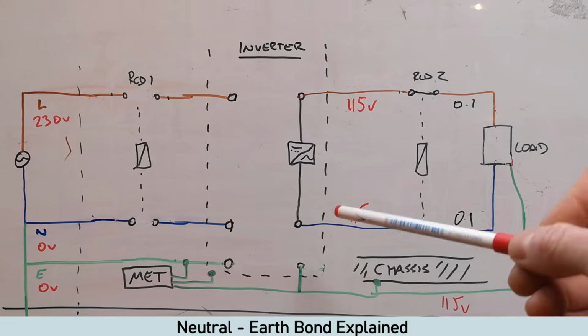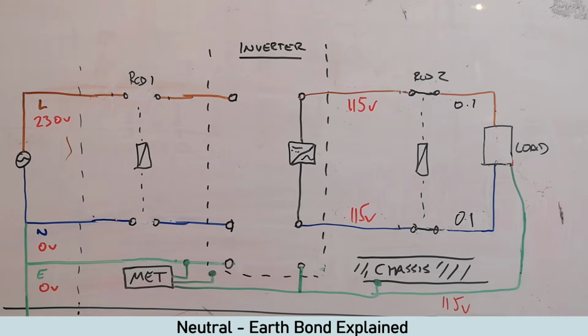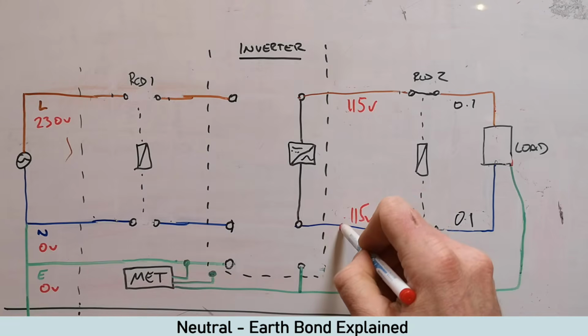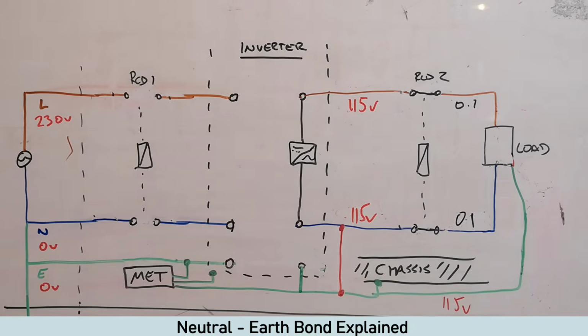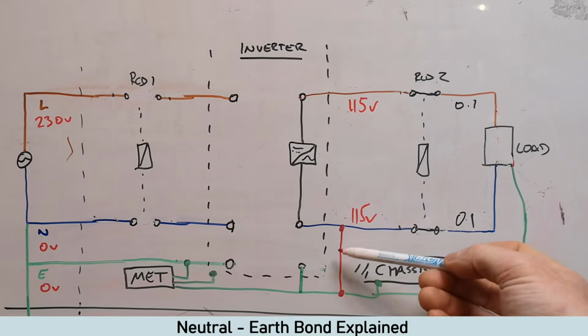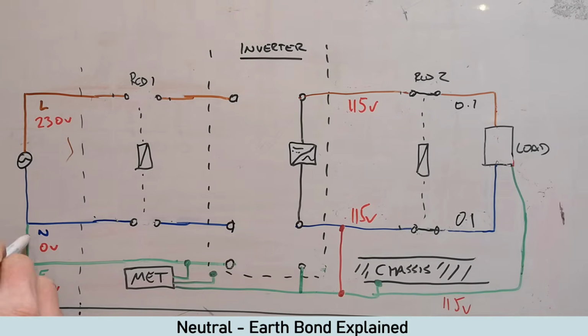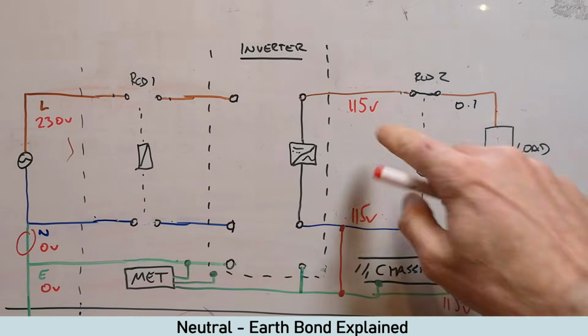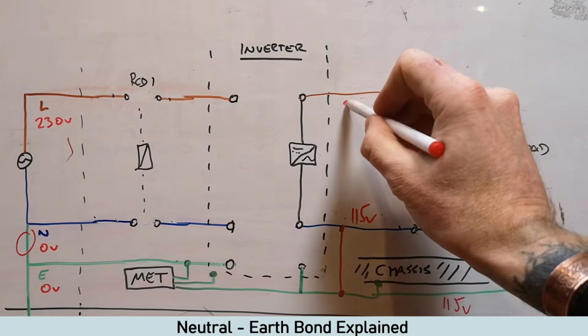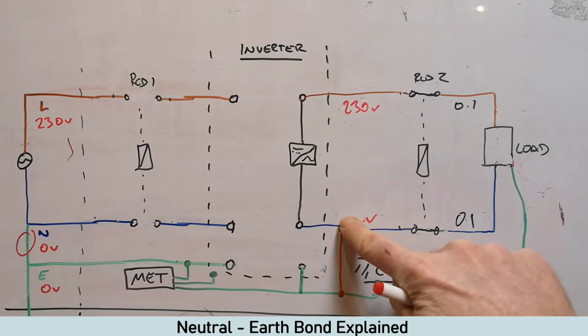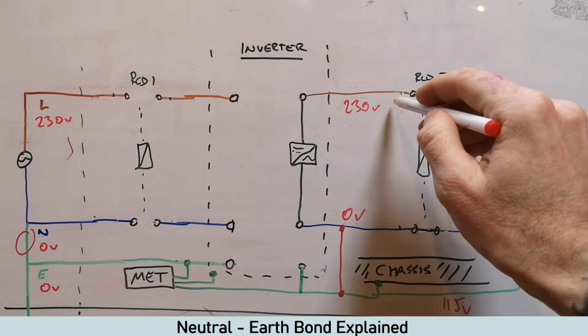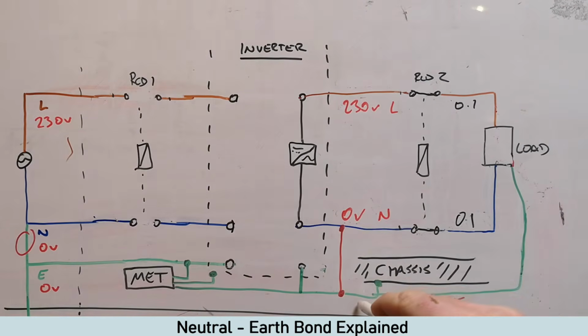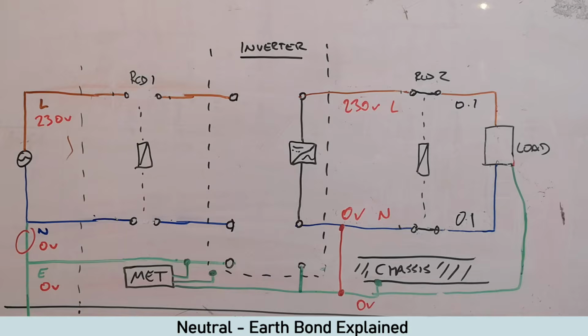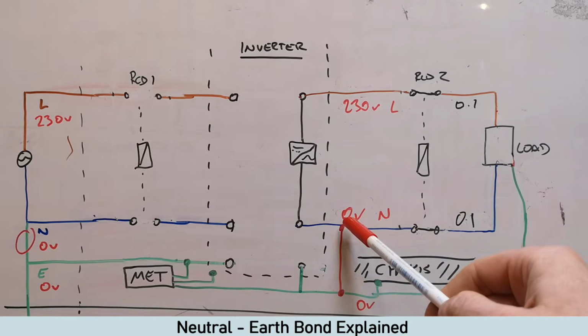So the way we get an RCD to function on this sort of unit is by bonding the neutral to the earth, like so. So this bond is the same as this bond. So that's your neutral to earth bond and that's your neutral to earth bond. So what's going to happen is that's going to go to 230, that's going to go to 0, a live and a neutral, and then obviously the earth there is 0 volts as well because they're combined. Then we're still disconnected from here, and now you're getting 230 and 0 volts.